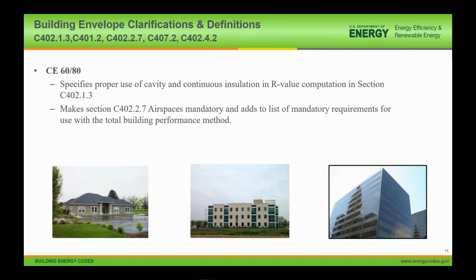There are a few other changes for the building envelope that clarify the proper calculation of R value for continuous insulation in section 402.1.3. And it also makes the section on airspaces a mandatory section. And as a reminder, the section on airspaces says that if an airspace is used for compliance with the IECC, those spaces need to be enclosed, unvented airspaces on the inside of the continuous air barrier.